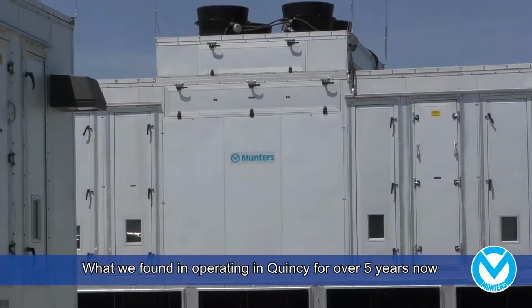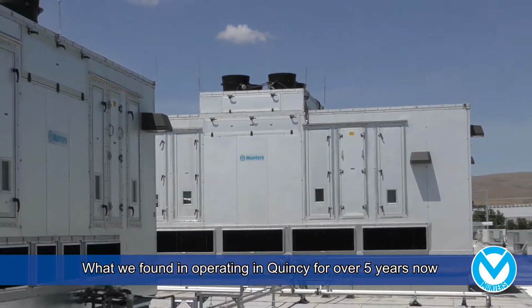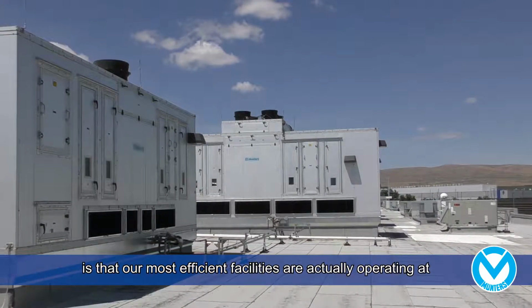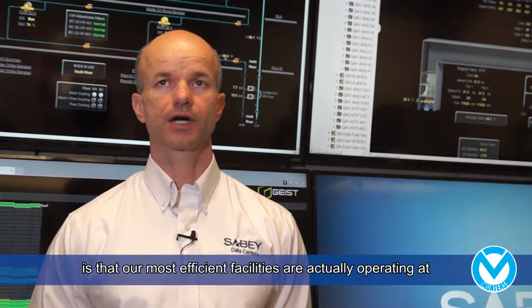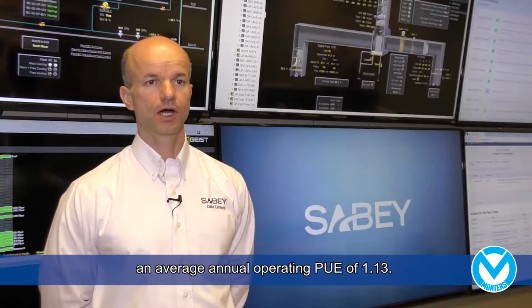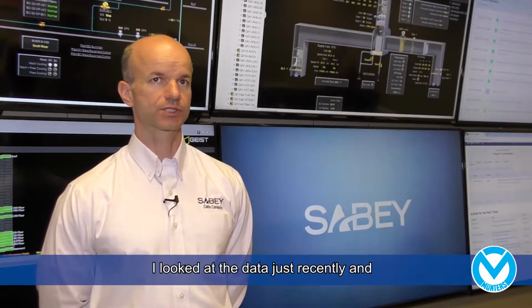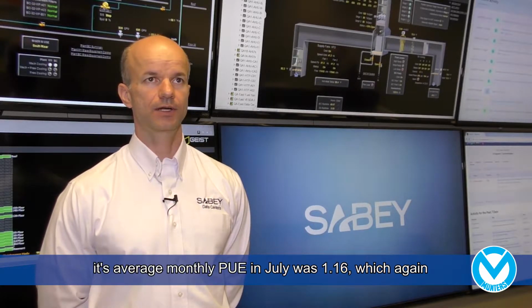And what we found after operating in Quincy for over 5 years now is our most efficient facilities are actually operating at an average annual operating PUE of 1.13. That particular facility, I looked at the data just recently, and its average monthly PUE in July was 1.16, which again...